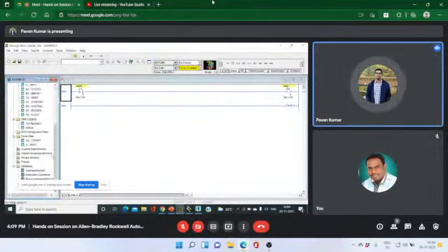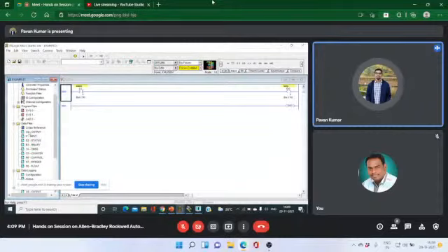And we can see here the data files. For that, output is represented by O, input is represented by I, status bit by S, binary bit is a memory bit which is B3, timer bit by T4, and counter by C5. These are the main requirements we use to build a program.